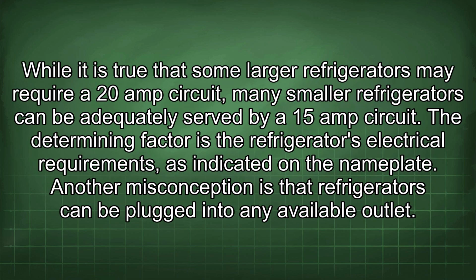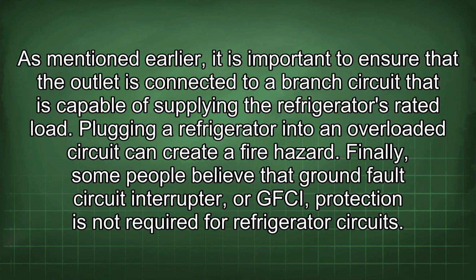While it is true that some larger refrigerators may require a 20-amp circuit, many smaller refrigerators can be adequately served by a 15-amp circuit. The determining factor is the refrigerator's electrical requirements, as indicated on the nameplate. Another misconception is that refrigerators can be plugged into any available outlet. It is important to ensure that the outlet is connected to a branch circuit capable of supplying the refrigerator's rated load. Plugging a refrigerator into an overloaded circuit can create a fire hazard.